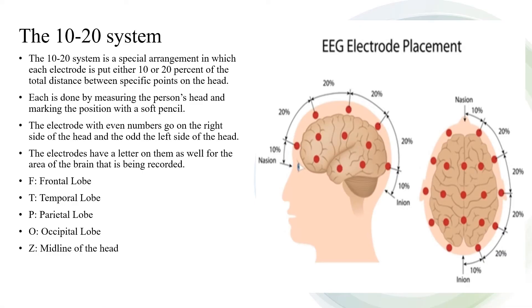The 10-20 system is a special arrangement in which each electrode is placed either 10 or 20% of the total distance between specific points on the head. Each position is determined by measuring the person's head and marking the position with a soft pencil. Electrodes with even numbers go on the right side of the head and odd numbers on the left side. The electrodes also have letters indicating the brain area being recorded: F for frontal lobe, T for temporal lobe, P for parietal lobe, O for occipital lobe, and Z for the midline of the head.